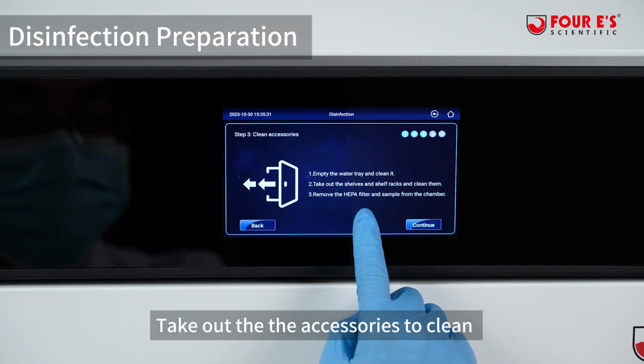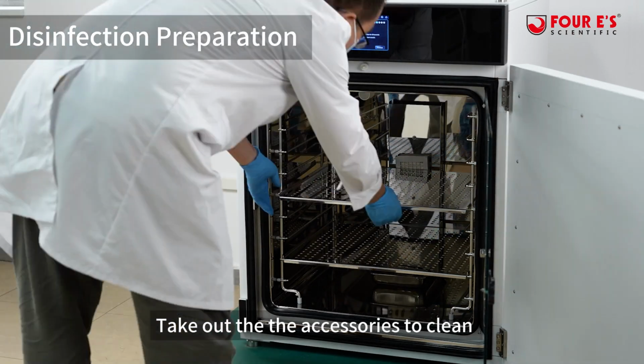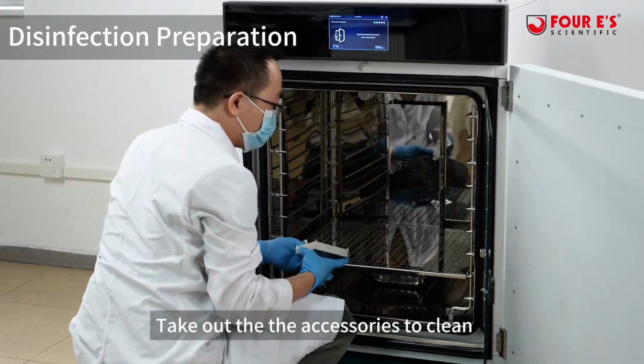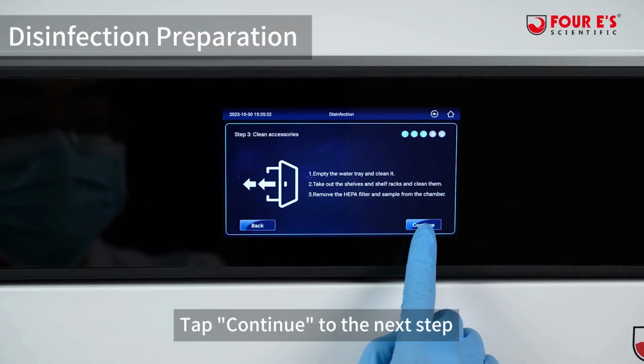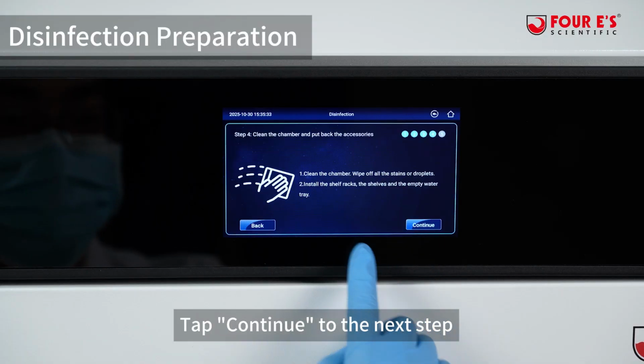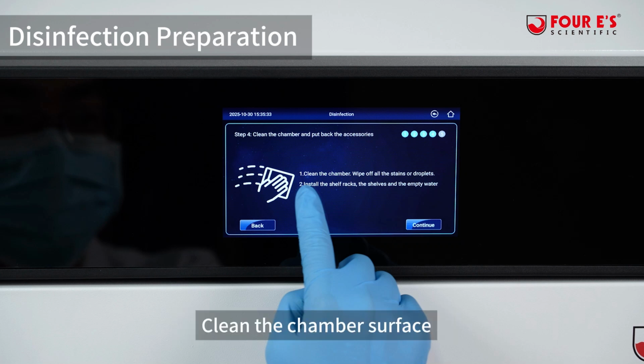Then take out the water tray, shelves and racks, and the HEPA filter to clean or replace. After taking out all the accessories, tap Continue to the next step. Next step will be cleaning the chamber surface with 75% ethanol and a cloth towel to remove the stains and droplets.